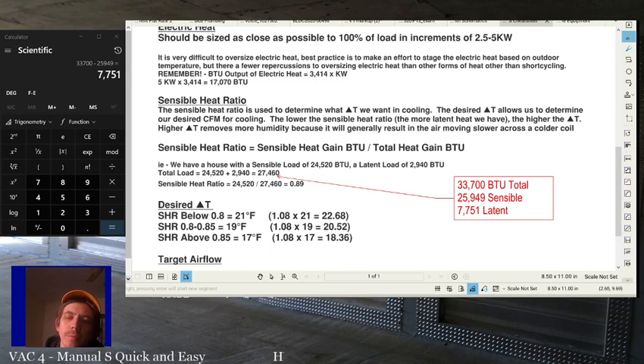So if you're going to equipment that's a higher efficiency, or it's just a different manufacturer, because it really changes manufacturer to manufacturer, if you can look up the expanded cooling data for the original equipment, you can compare that to your new equipment and make sure you're doing as good or a little bit better than that. Because it changes over time, right? All these numbers tend to change a little bit over time, and newer equipment's going to put out closer to nominal BTUs, and that's going to affect what you're putting in.